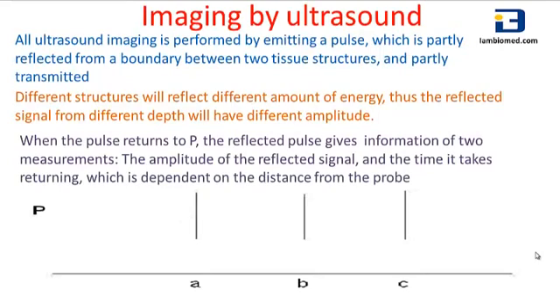When the pulse returns to P, the reflected pulse gives information of two measurements: the amplitude of the reflected signal, and the time it takes to return, which is dependent on the distance from the probe.